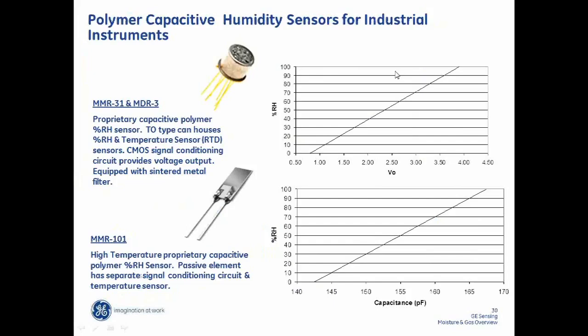There's some people in the industry that say that these sensors were discovered by accident, that somebody was using polyimide as a conformal coating on circuit boards, and they noticed when they were testing the circuit boards that there was a variation due to what they originally thought was temperature, but when they did some further studies in environmental chambers, they found that they had almost a direct proportionality to humidity, and they figured out that the polyimide, if cured under certain conditions, could actually become a humidity sensor. So a lot of it was derived from that. I don't know how true that story is, but that's the story I heard.